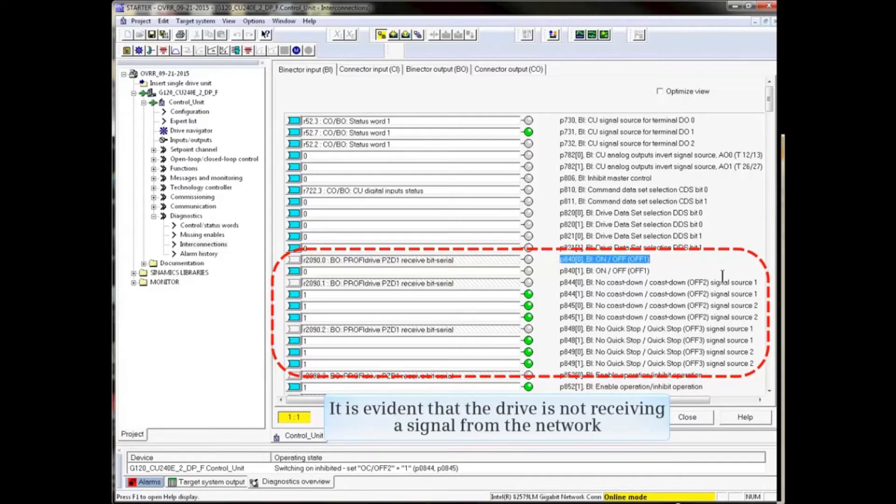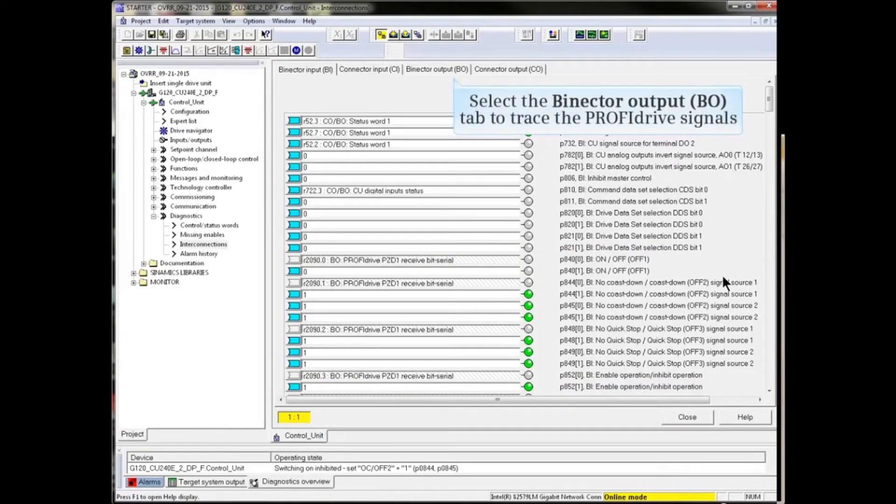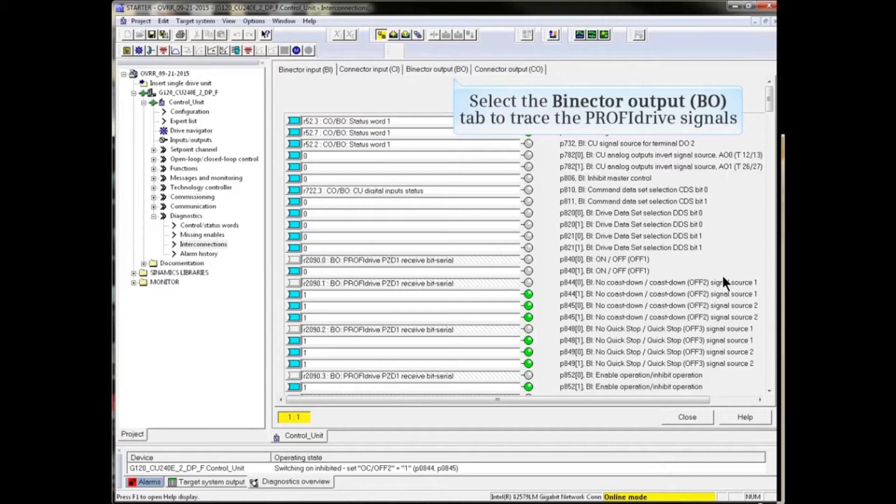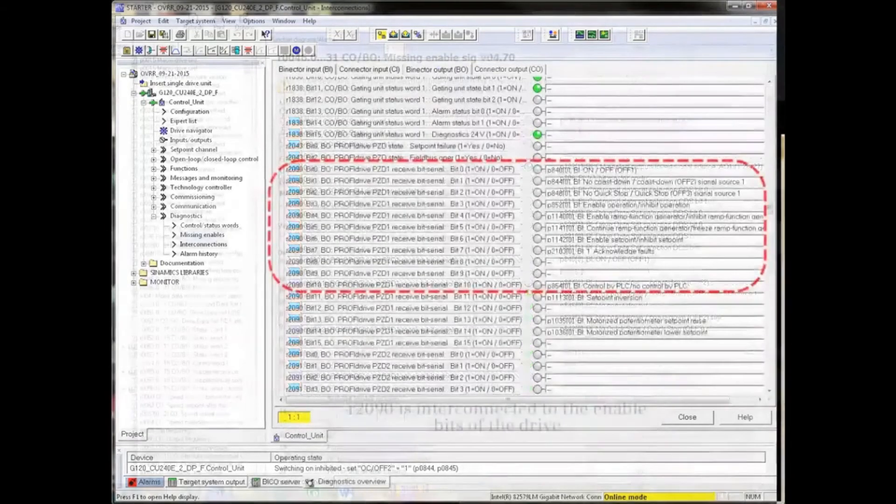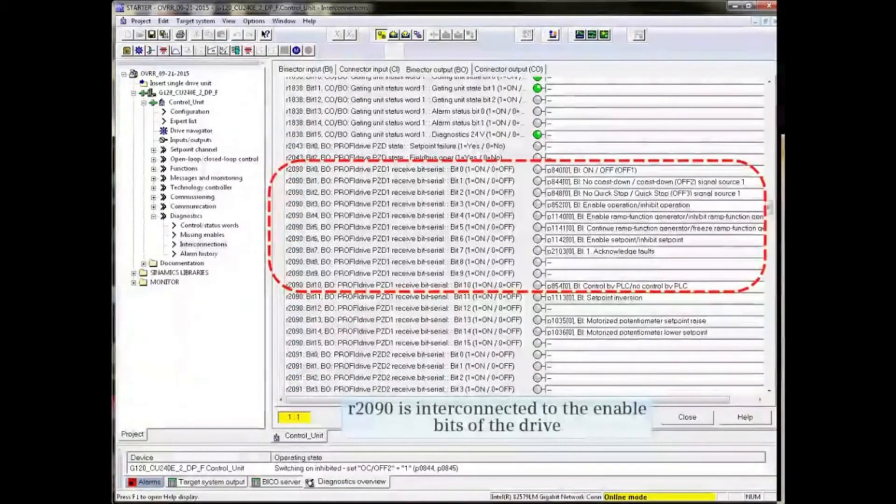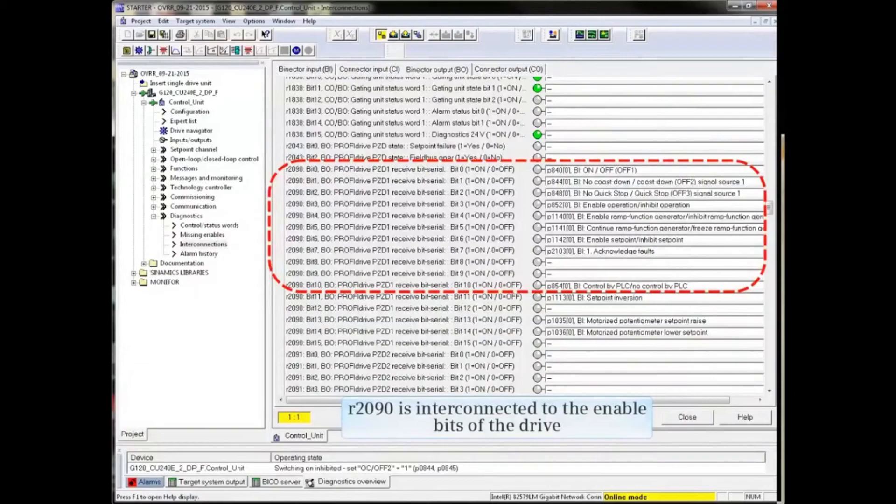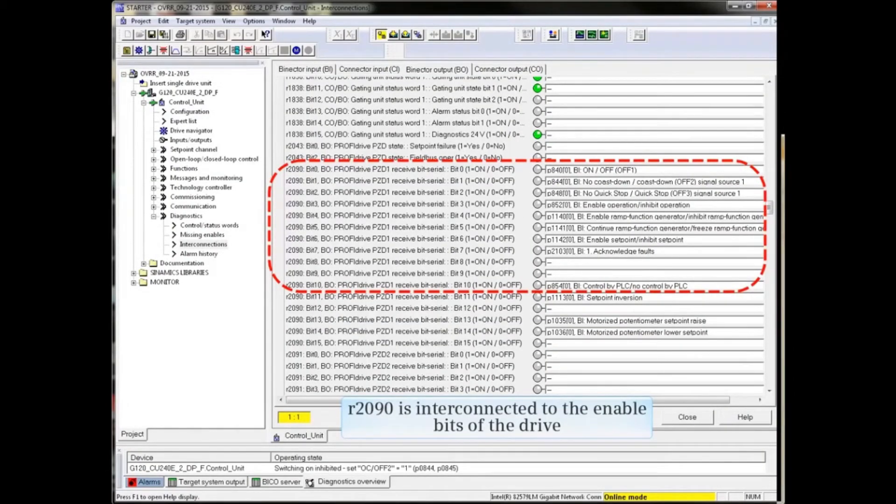In reverse order, we could trace the PROFIDRIVE signals by clicking the Binector Output tab and see that r2090 is interconnected to the enable bits of the drive.